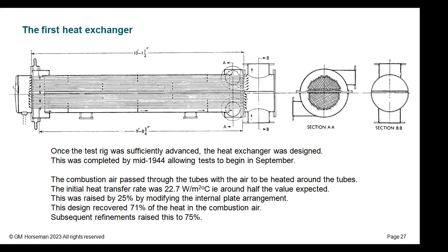And when they built this, the first heat transfer rate they achieved was 22.7. I put it in modern units, watts per square meter centigrade. I used to work in BTU per hour square foot Fahrenheit, and it's a nice round number of 4 in those units. That's what was achieved when they hoped to get 8. So it's about half of what they expected.